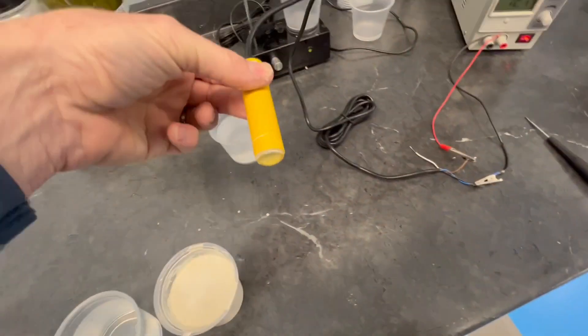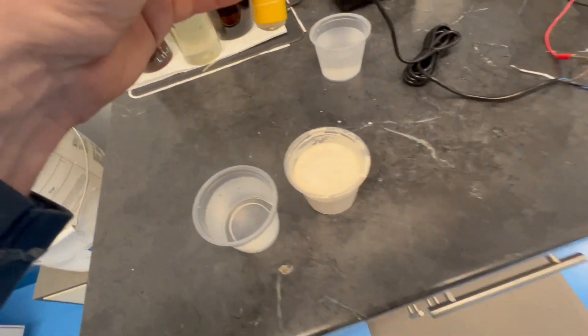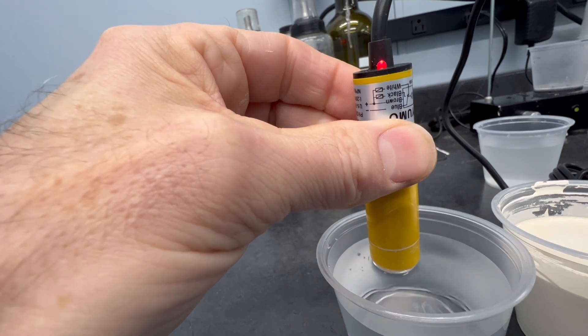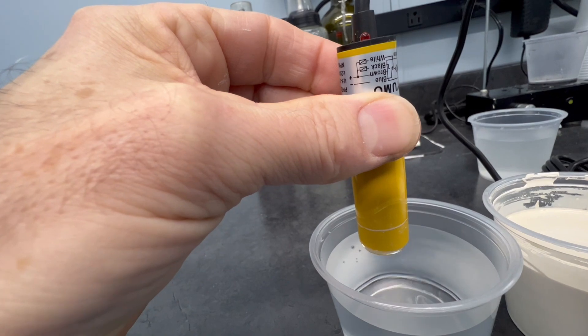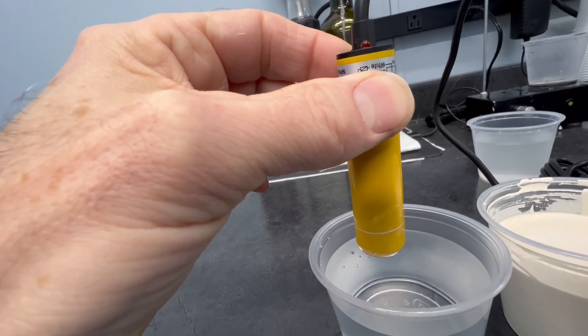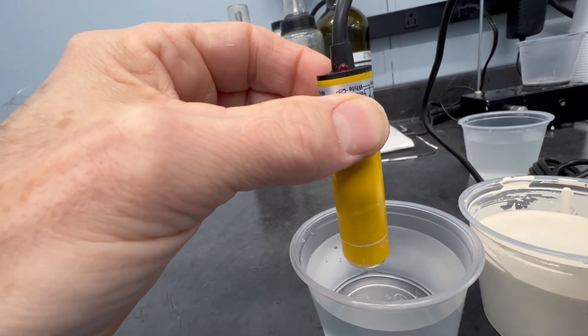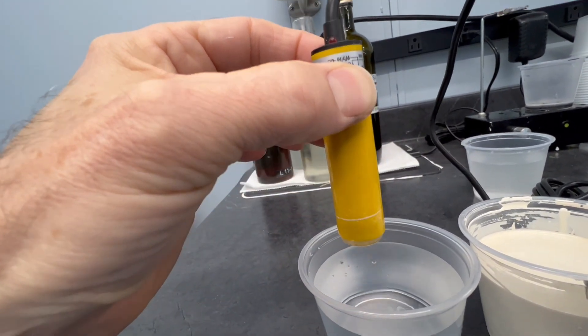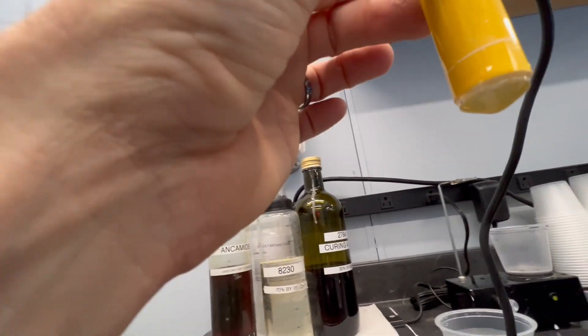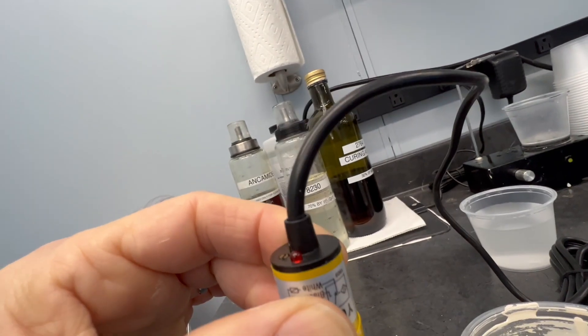So here's the setup. I have a sensor not in the pipe, just for test purposes and to demonstrate how it works. You'll see the light go on, so it's just barely making contact with the liquid. The difficulty is getting it to unsense the liquid after it's sensed it, even though there's something clinging on - there's liquid clinging to the bottom of the lens. That drip isn't causing it to sense, and that's part of the calibration.